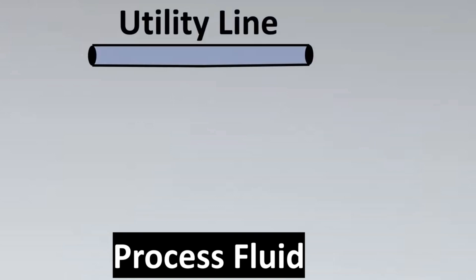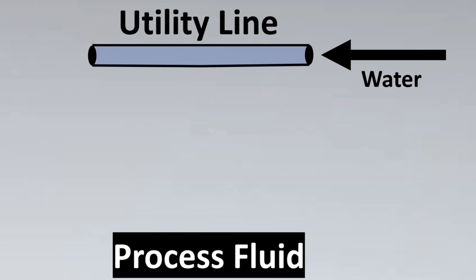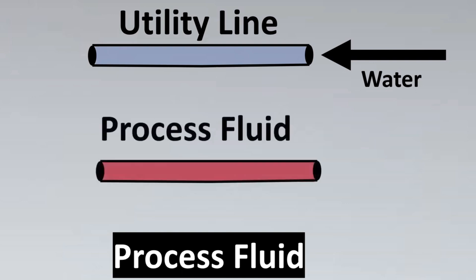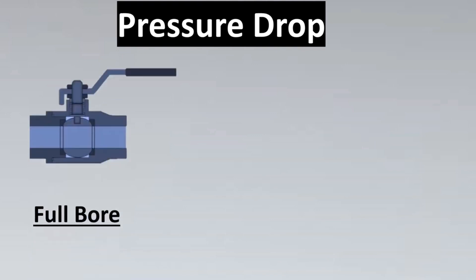The next case is the process fluid. As a rule of thumb, for utility lines carrying water, it is generally recommended to go with a reduced bore valve — this depends on the client's design basis, but you can usually save project cost this way. For process fluids, it depends on how critical they are — for example, certain acids or viscous fluids may require full bore valves.